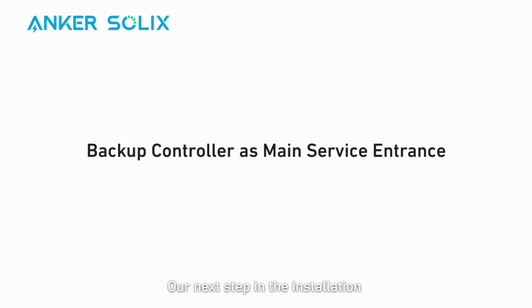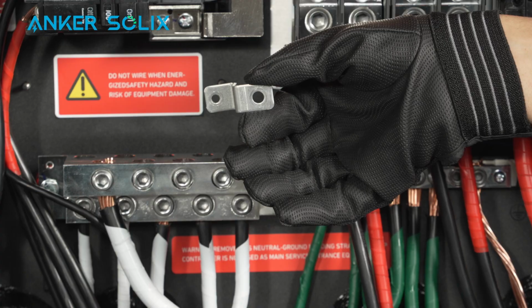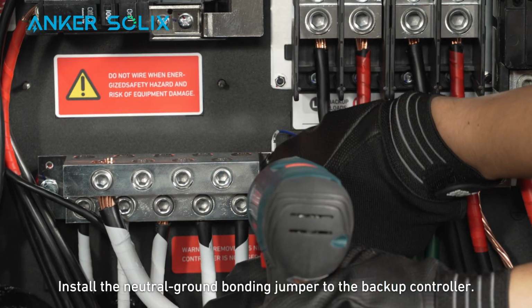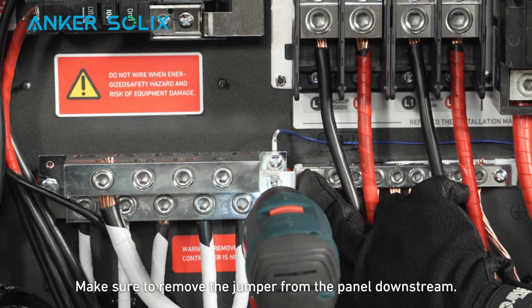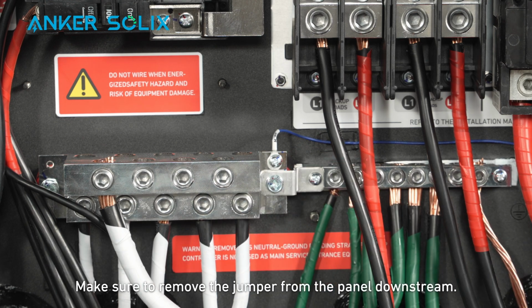Our next step in the installation depends on how you use your backup controller. If it's the main service entrance, follow these steps. Install the neutral ground bonding jumper to the backup controller. Make sure to remove the jumper from the panel downstream.